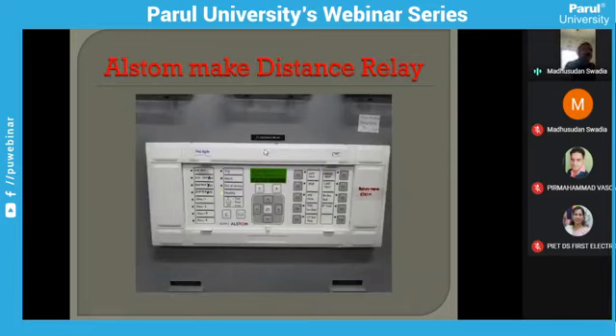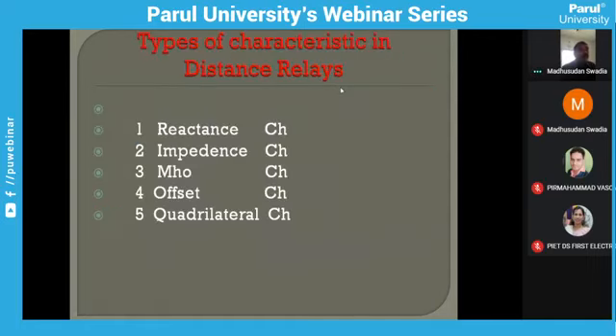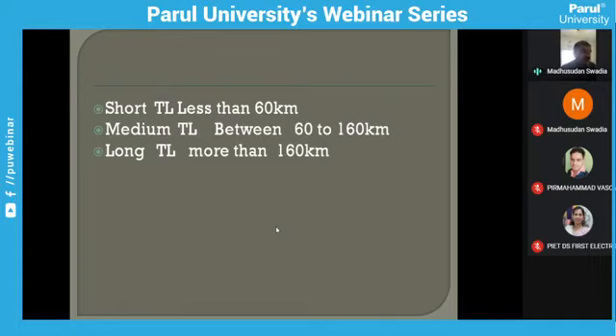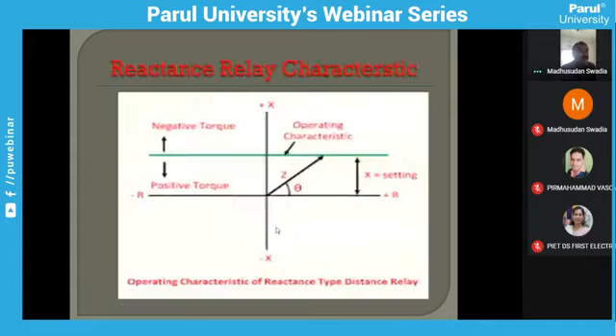There are different characteristics used in distance relays. There are three types of lines: short transmission lines up to 60 km, medium lines from 60 to 160 km, and long lines beyond 160 km, each with different relay characteristics. The reactance characteristic uses the Y-axis only — it is a straight line on the R-X impedance diagram, non-directional, with no effect of arc resistance, but covers a large area in the R-X plane, so mal-operation due to power swing is observed. The impedance characteristic is a circle passing through all four quadrants around the origin — the area within is the operating region and outside is the restraining region.